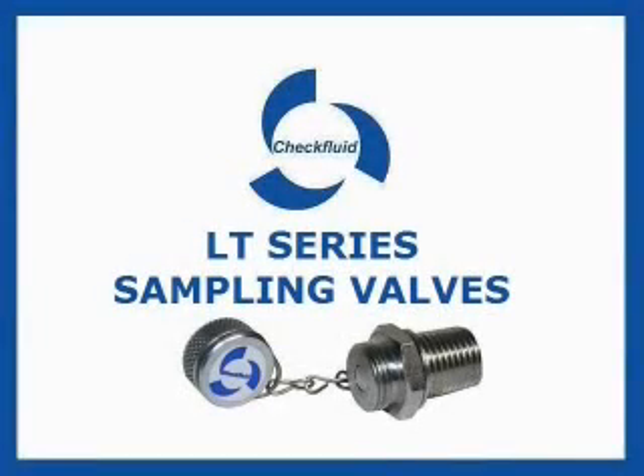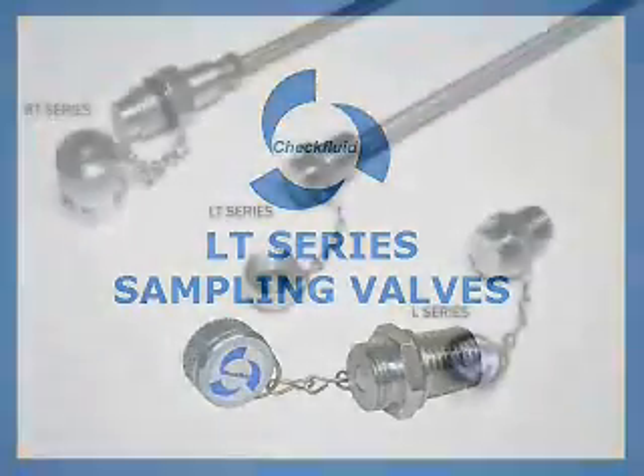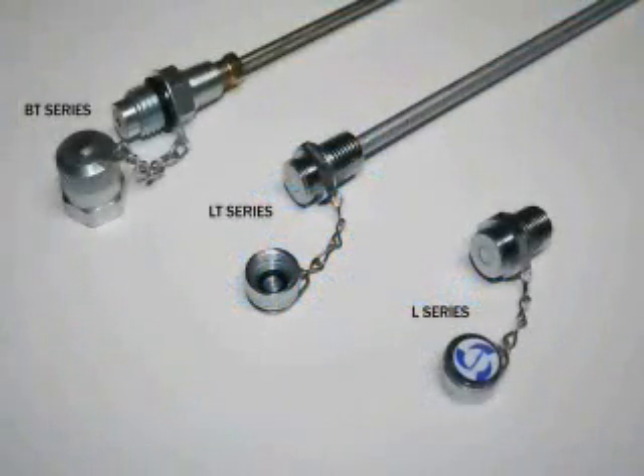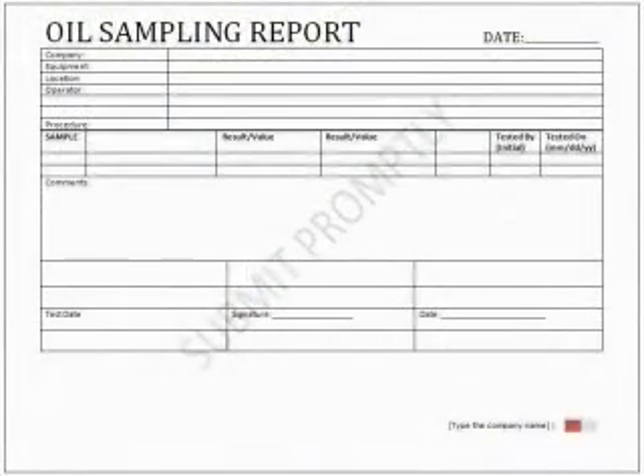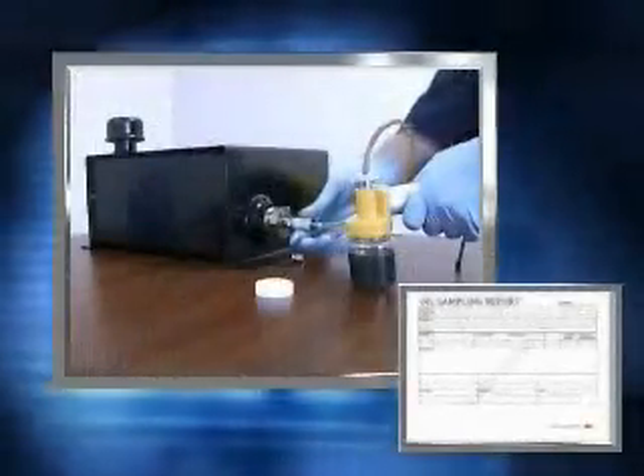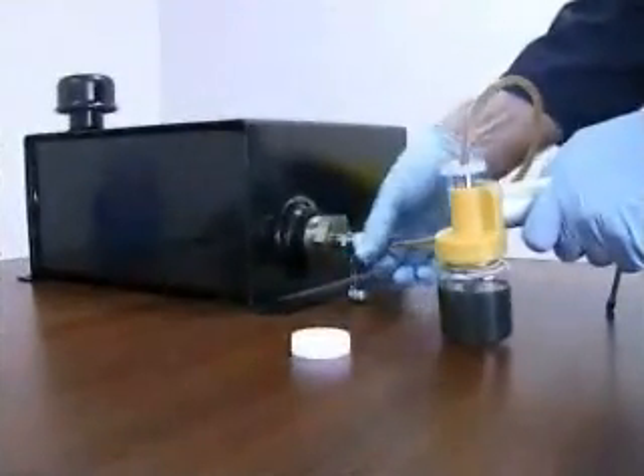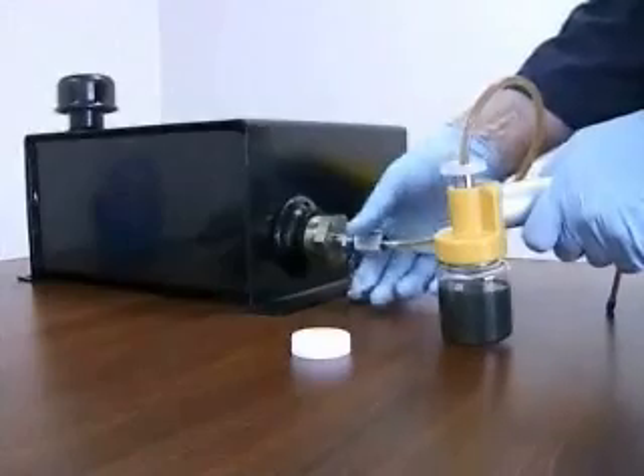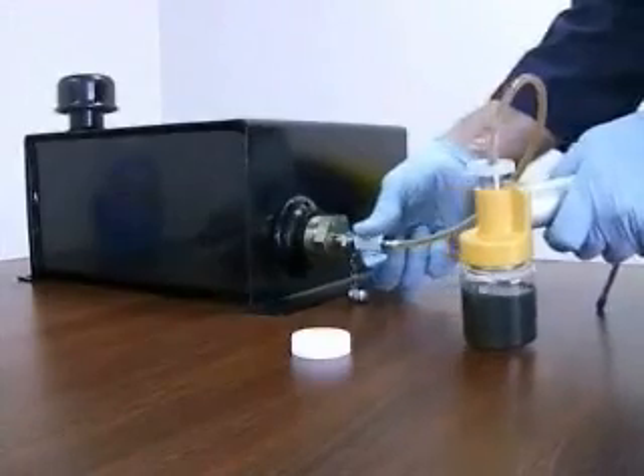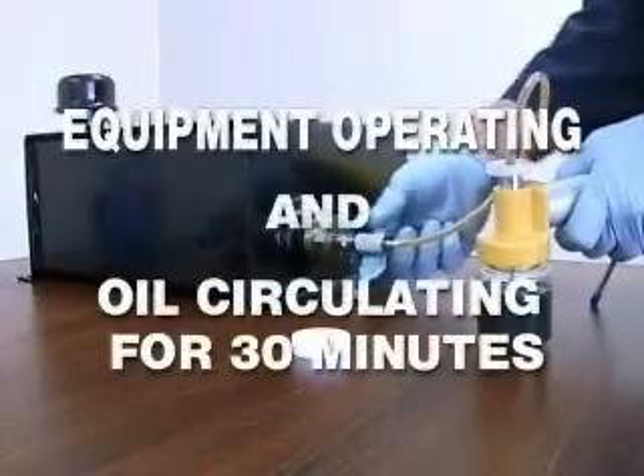In this 3-minute video, we will show how to use the Checkfluid LT Series high-flow sampling valve to draw a representative oil sample that can be accurately analyzed time over time. The LT is permanently mounted to draw the most active oil while the equipment is running.